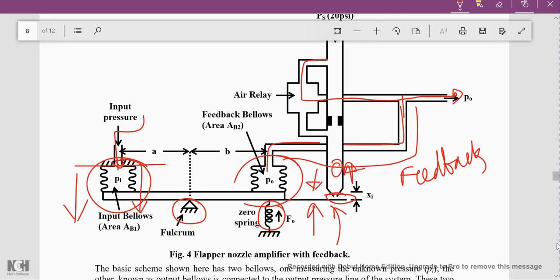Because of the increase in pressure, the output pressure increases. This output pressure is again monitored — that increase in output pressure increases the pressure in bellow 2. When the pressure inside bellow 2 increases, expansion takes place again, and it starts moving in the opposite direction, pushing the flapper back, so the displacement returns to its original position.